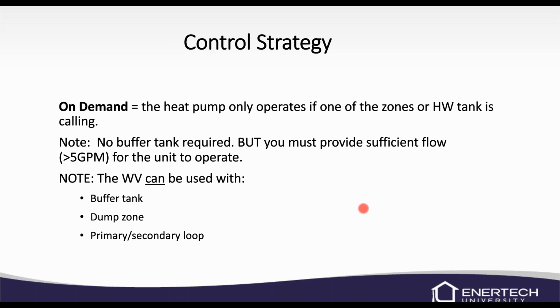But we've just found over time, air is a big problem when you guys are piping these things in, and that's our biggest issue: flow. And so we found that if we have air handlers that are smaller than 2 tons, we have issues with water flow rates. And so we would recommend a buffer tank in that application. Anytime we're using an air handler that's larger than 2 tons, we would recommend using the hydraulic separator. Now, we'll get into some piping here in just a few minutes, and you'll be able to see that. That's also in the IOM, so always, if you've got questions, refer to the IOM.